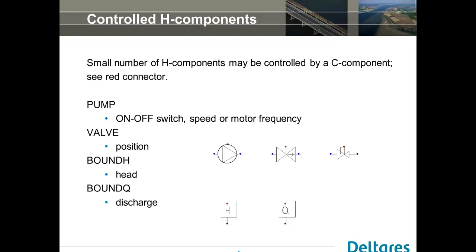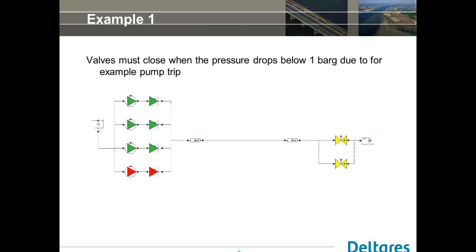That was very briefly the background of the control module of Wanda. Now we want to show it in action - we're going to look at the system which we want to control. Here's a pumping station, pipeline, and two valves. Basically, what can happen is we have a full pump trip. The pump trip can send a pressure wave going into your pipe. Then at a certain moment you want to close these valves to minimize the minimum pressure - for example, you want to close it if the pressure drops below one bar.